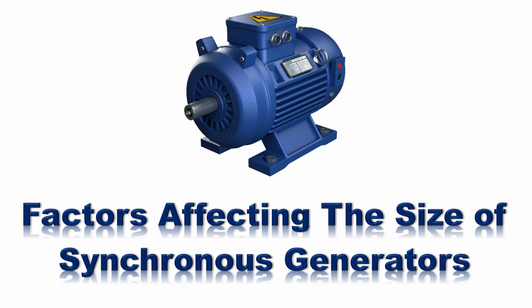Because the size of the generator is not just a mechanical issue. It is directly connected to efficiency, losses, and cooling. As generators become larger and their power rating increases, their efficiency improves, which is a big advantage in large stations since it leads to huge fuel savings. At the same time, increasing the generator rating changes its size and power density, and this creates thermal challenges.